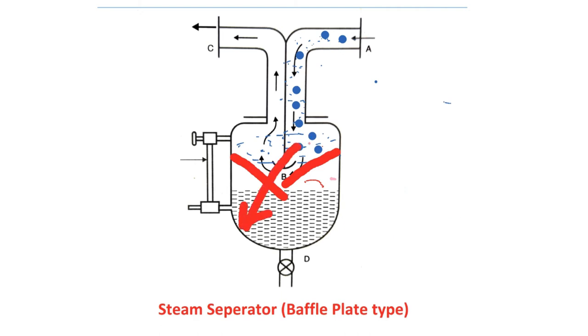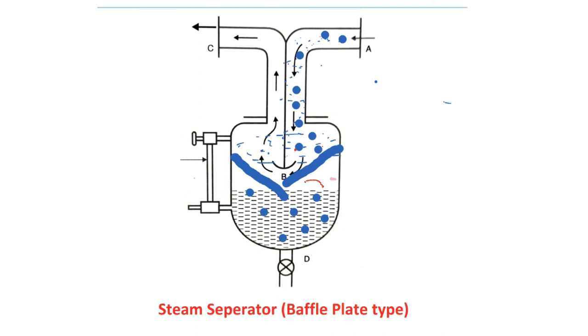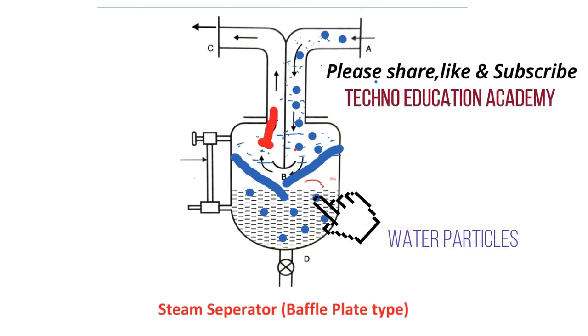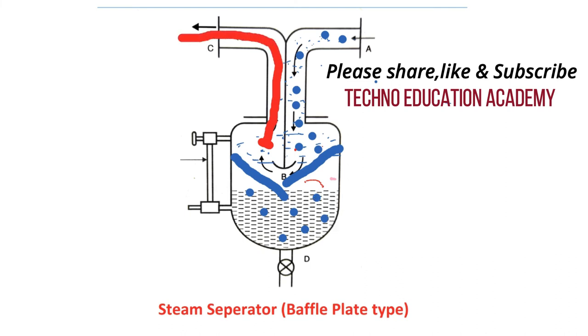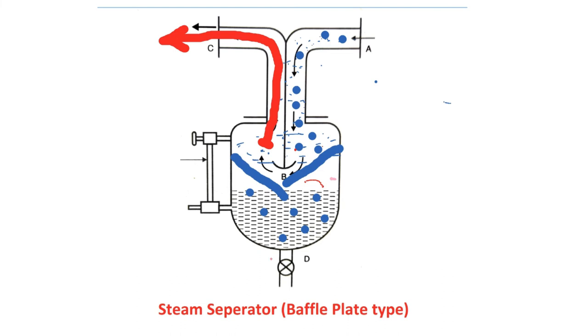Water particles have greater density — steam occupies approximately 1600 times the volume of water, so steam particles have light density while water particles have higher density. Due to inertia, the water particles fall down to the bottom of the separator. The drier steam is discharged through flange C. To see the level of water collected, a water gauge is provided, from which the water level in the separator can be read.